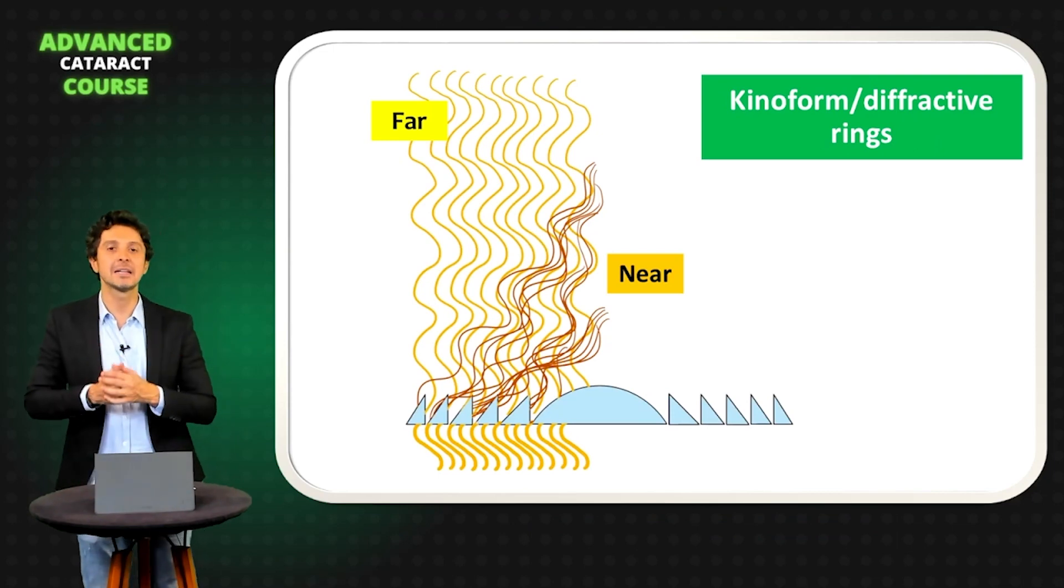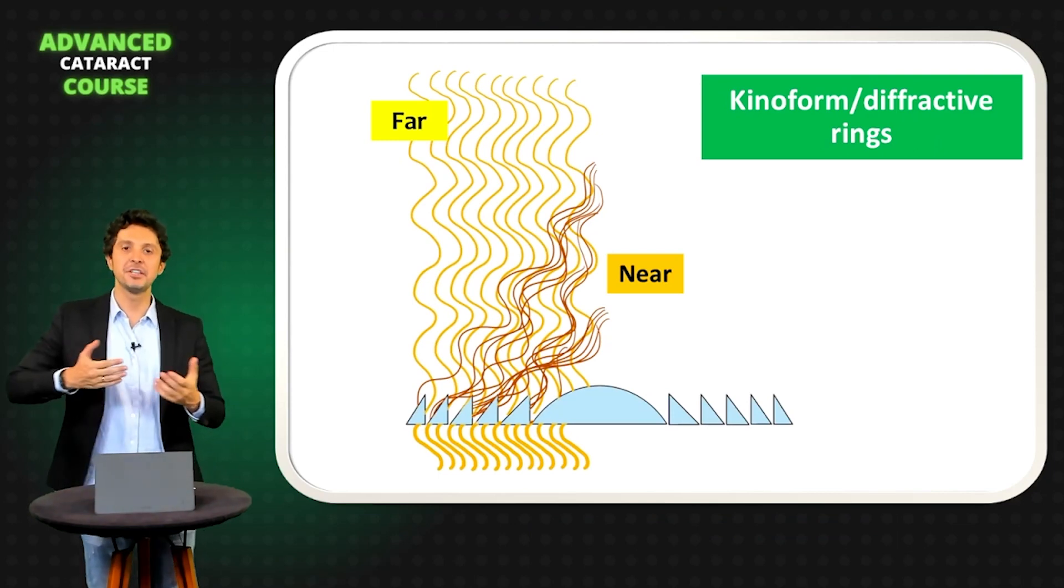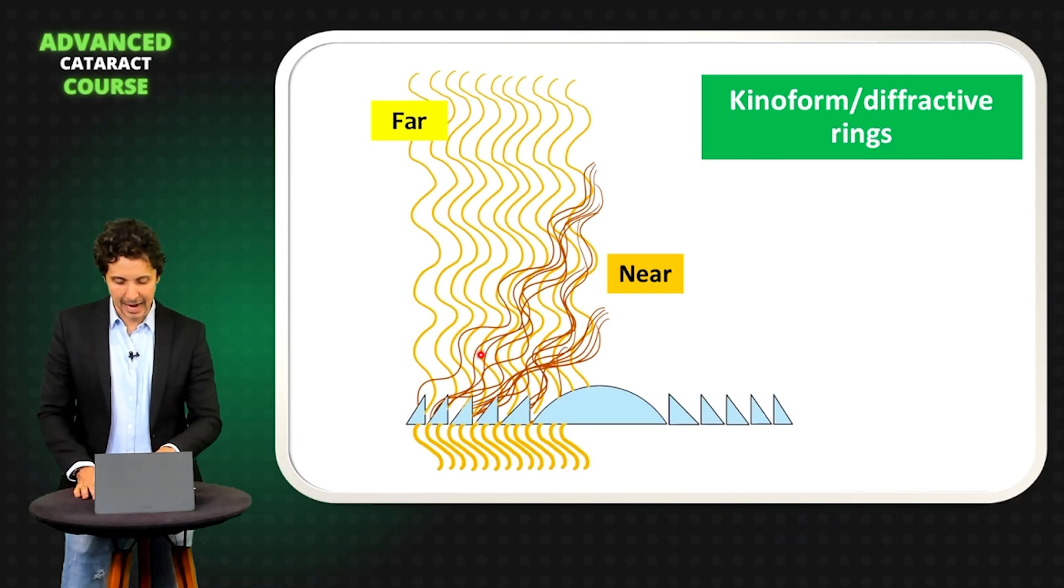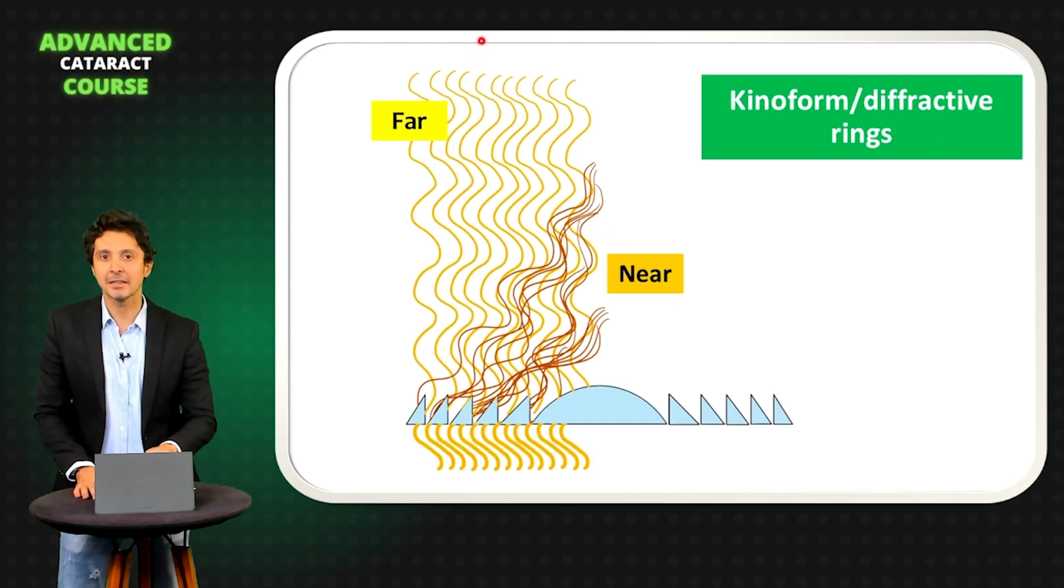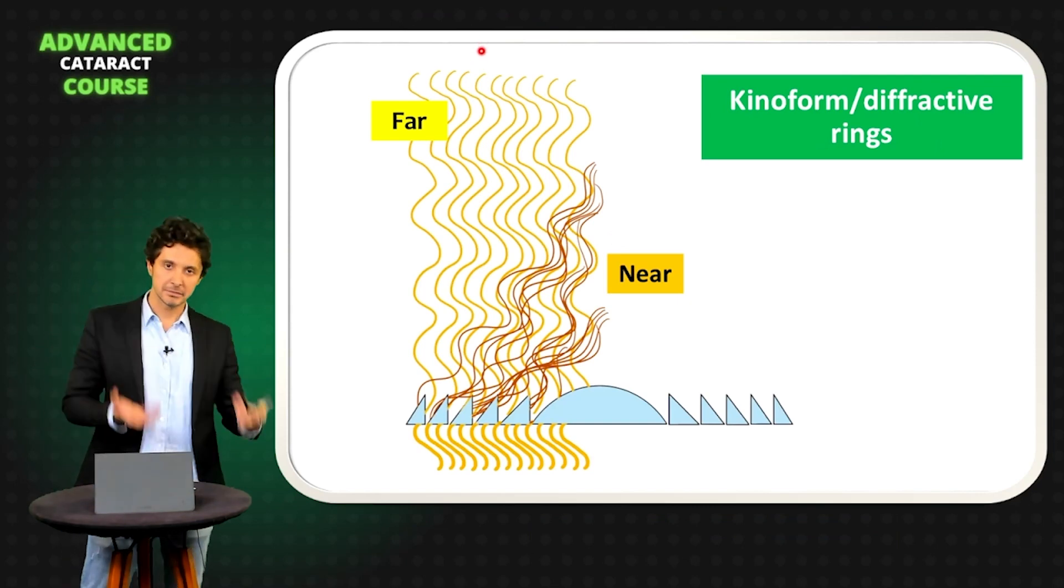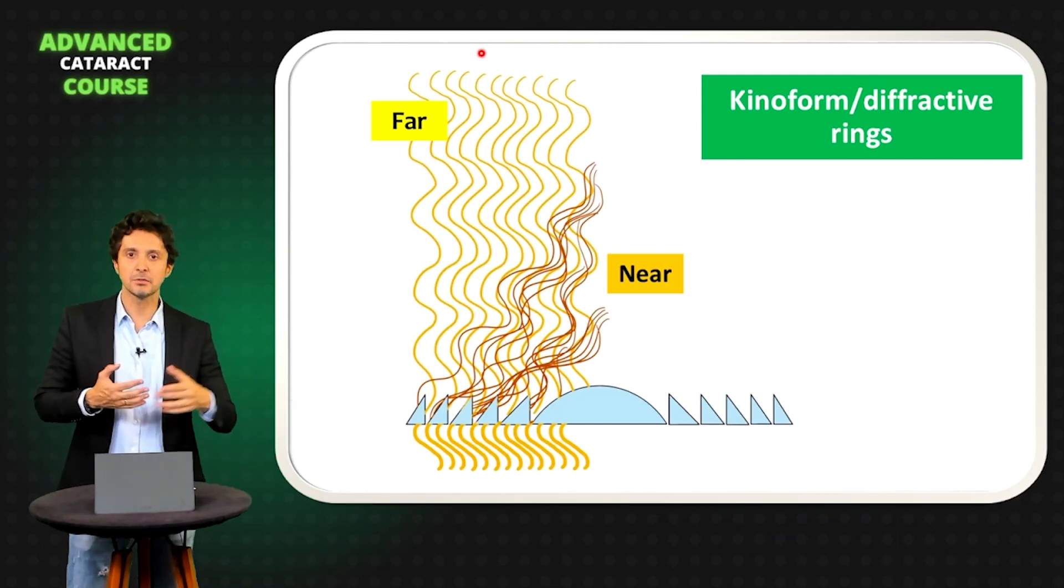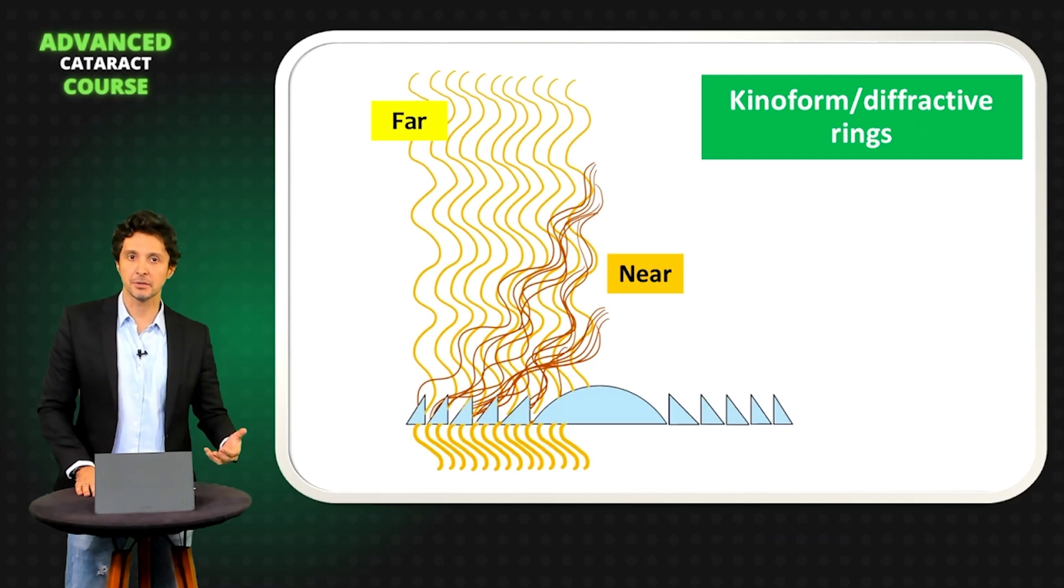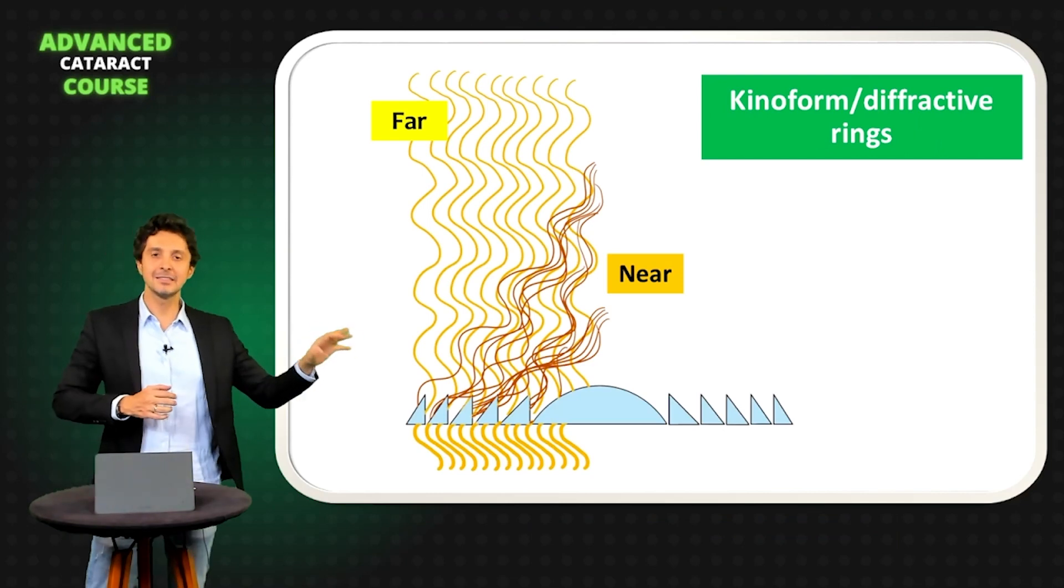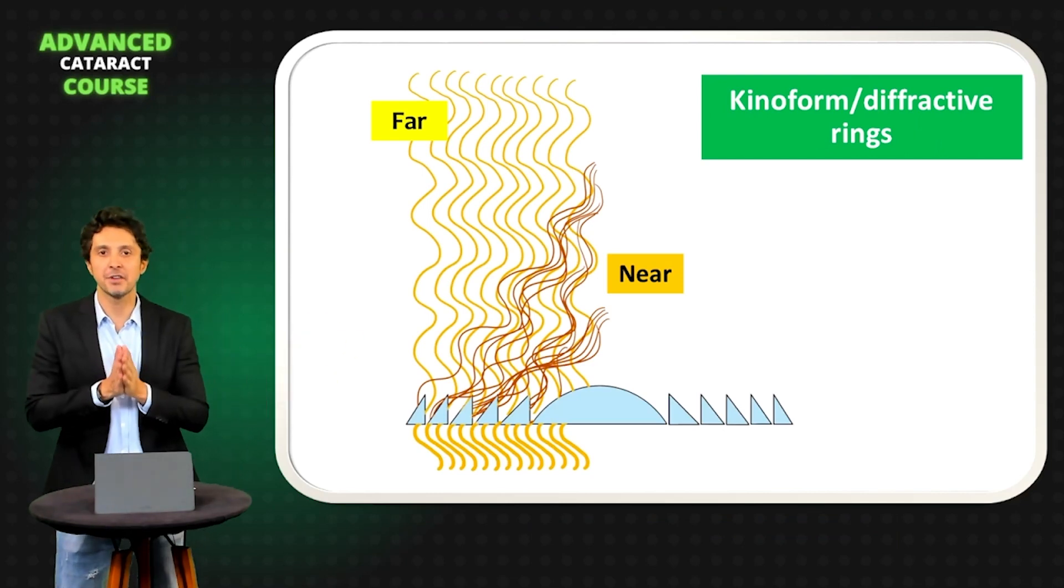What happens when the light came to these diffractive rings? Part of the light goes to near, as you observe here, and part of the light goes far. And because of this split of light, this light split, you can have the night symptom. This is the base of a diffractive IOL.